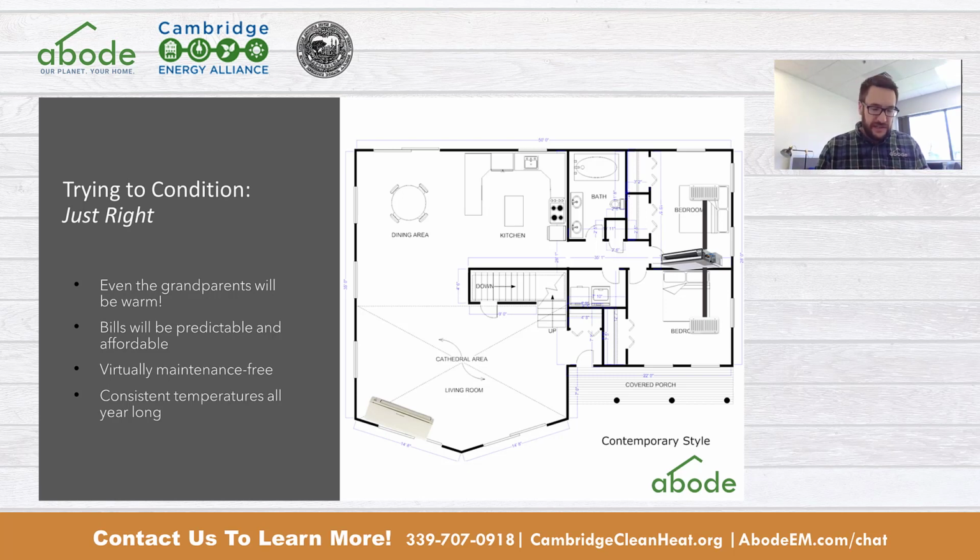And to be able to do this, you're going to need to start with the heat load, figuring out exactly how much that room or those rooms, those zones, or those homes use, and then figure out how much equipment you're going to need to meet that number. So instead of putting in a unit in each and every bedroom or just having 1 unit for the entire house, this is really the approach that we're talking about. Let's just use 1 ductless unit to cover all the living space and then 1 ducted unit to cover the bedrooms. And this really does lead to these systems operating at the highest coefficient of performance.